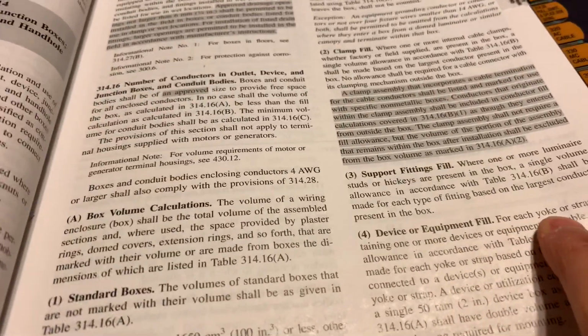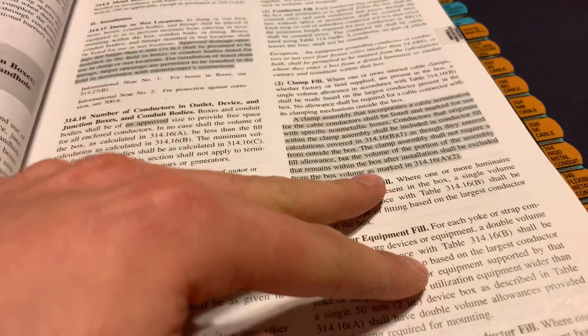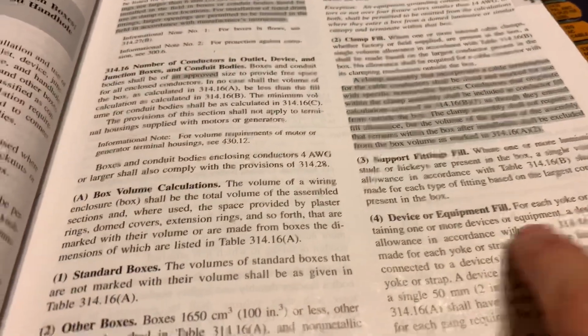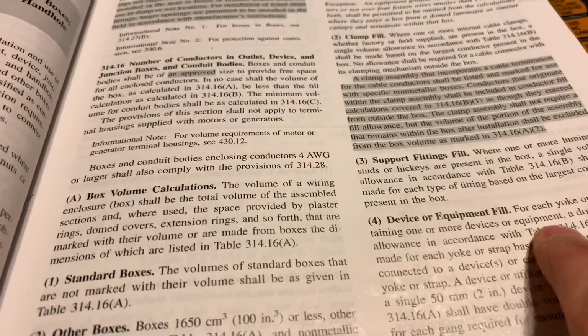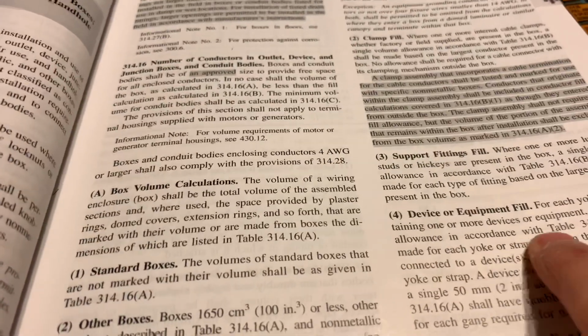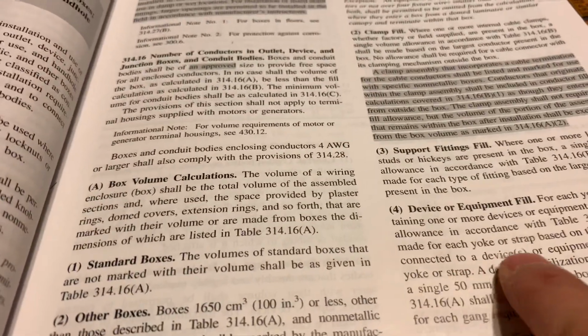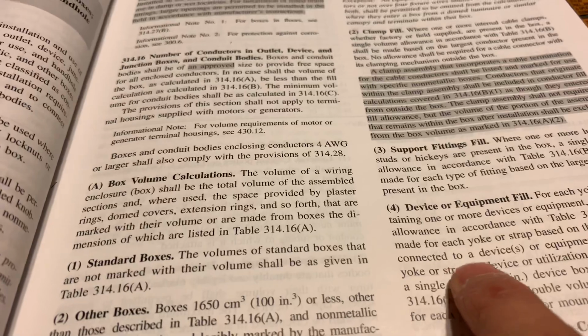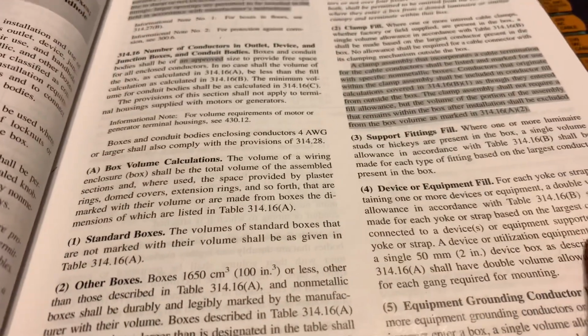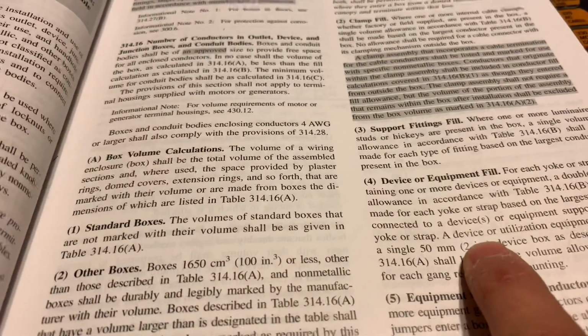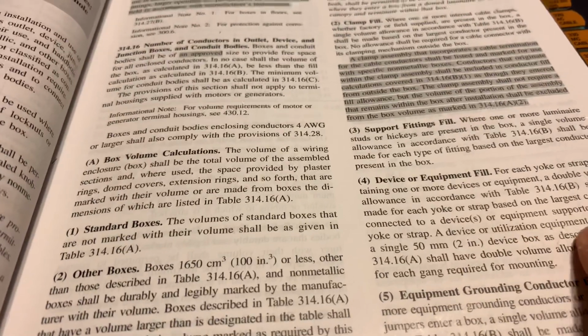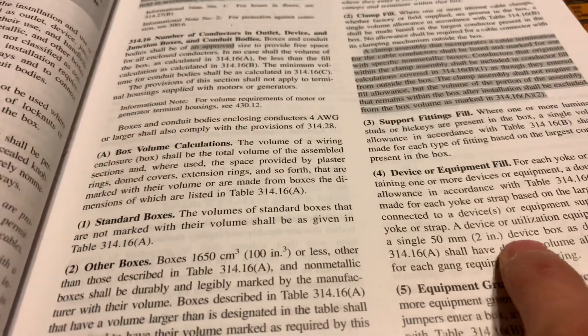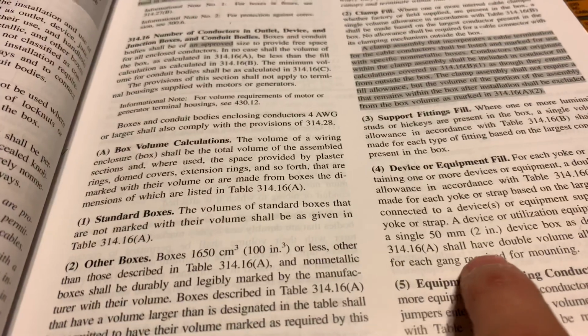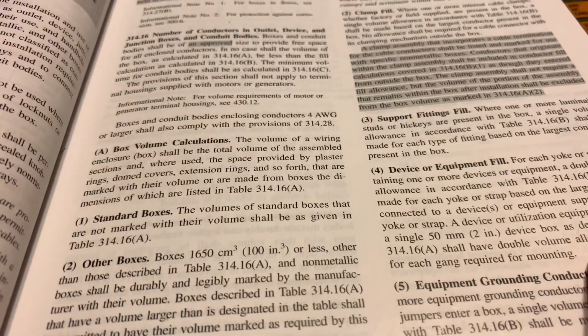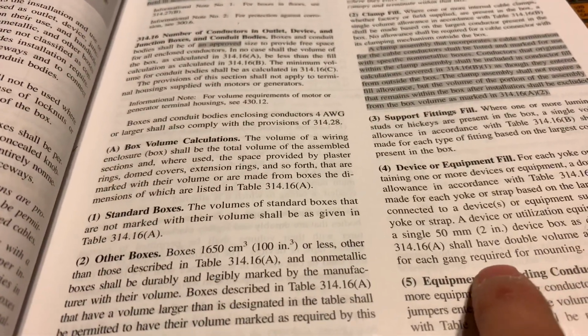So for each yoke, which means per two screws or whatever, so each yoke or strap containing one or more devices or equipment, a double volume allowance in accordance with the table shall be made for each yoke or strap based on the largest conductor connected to the device or equipment supported by the yoke or strap. A device or utilization equipment wider than a single 2-inch device described in the table shall have double volume allowances provided for each gang required for mounting.